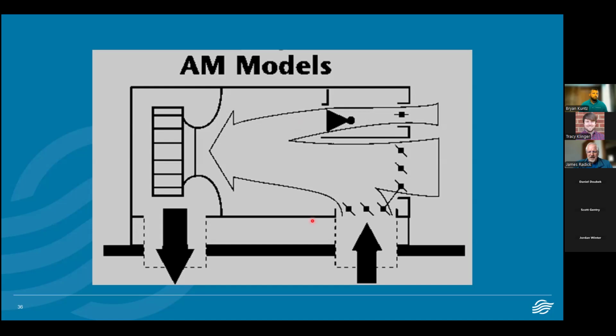The other 80% of that fan capacity can be made up of either return air or outside air. You can see the link between those dampers. Any mixture thereof, what your building needs. Okay, so that's an example of an air management unit and how it accomplishes what you're looking at. And basically, air rotation, air turnover, that's a decent concept. What we've done is taken it a step further. By pressurized air rotation, you're moving a lot of air. That allows you to get to the low discharge temperatures that you would see. But it doesn't do anything for that positive pressurization, making up that air that a building needs to manage it. This system, if you think about it, is a modulating makeup air married to an air rotation unit. You're getting the best of both worlds with this type of unit.